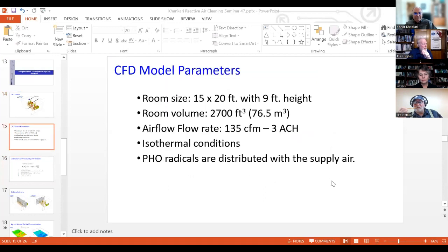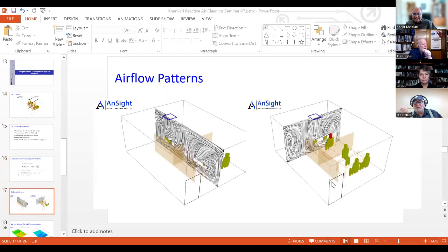Now, if you look at the airflow patterns, irrespective of whether you have a reactive agent or no agent, you can see as this air comes out from the diffuser, it bumps on this wall and creates a recirculation zone. That means this is a stagnant zone, air is just sitting there and circulating. In this case, there are two opposite circulation patterns. The airflow patterns are much more complex in three dimensions. We need to slice them out to understand what is happening here.